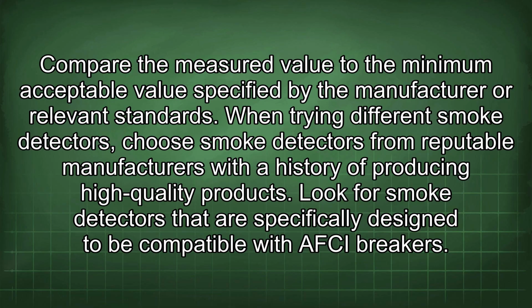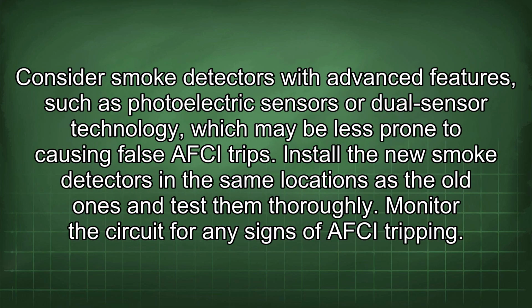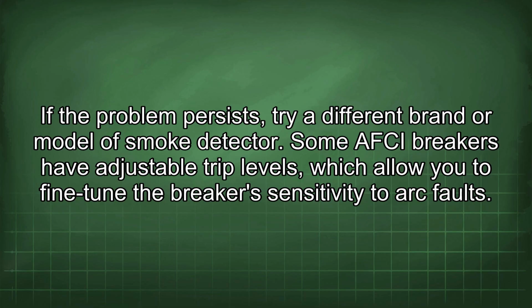When trying different smoke detectors, choose smoke detectors from reputable manufacturers with a history of producing high-quality products. Look for smoke detectors that are specifically designed to be compatible with AFCI breakers. Consider smoke detectors with advanced features such as photoelectric sensors or dual sensor technology, which may be less prone to causing false AFCI trips. Install the new smoke detectors in the same locations as the old ones and test them thoroughly. Monitor the circuit for any signs of AFCI tripping. If the problem persists, try a different brand or model of smoke detector. Some AFCI breakers have adjustable trip levels which allow you to fine-tune the breaker's sensitivity to arc faults.